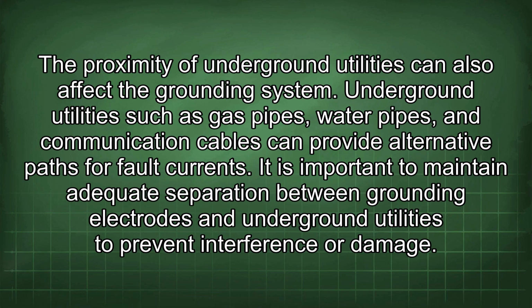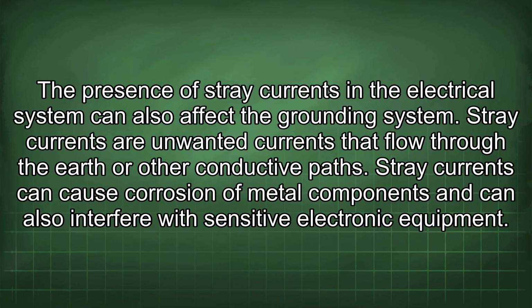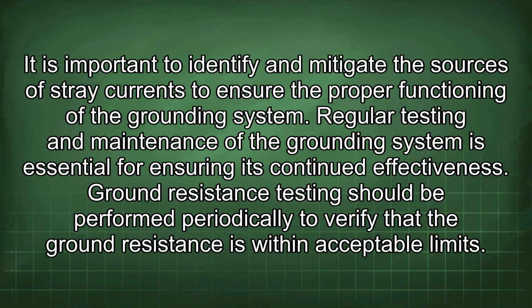The proximity of underground utilities can also affect the grounding system. Underground utilities such as gas pipes, water pipes, and communication cables can provide alternative paths for fault currents. It is important to maintain adequate separation between grounding electrodes and underground utilities to prevent interference or damage. The presence of stray currents in the electrical system can also affect the grounding system. Stray currents are unwanted currents that flow through the earth or other conductive paths. Stray currents can cause corrosion of metal components and can also interfere with sensitive electronic equipment.